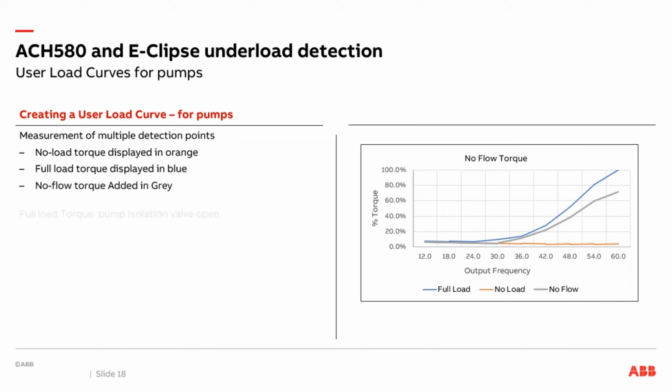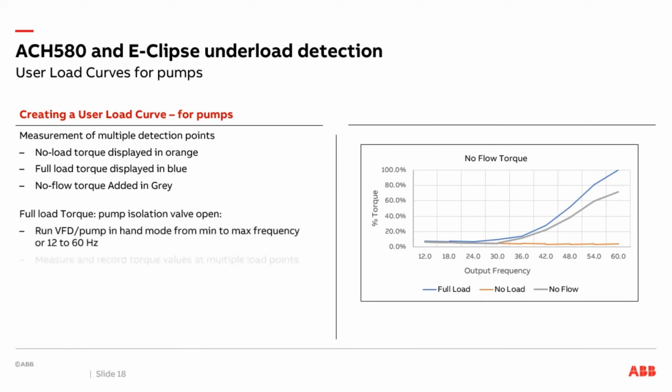We measured full load torque by operating our pump in the hand mode. Torque values were recorded at 6 Hz intervals, and once this data was complete, the drive was stopped.